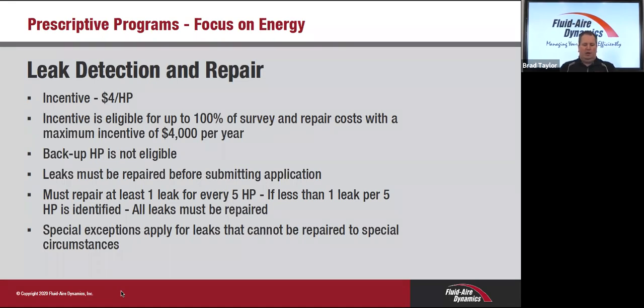So Focus on Energy has offered an incentive of $4 per running horsepower. This does not include backup compressors in that number. The incentive is eligible for up to 100% of the survey and repair costs with a maximum incentive of $4,000 per year. Leaks must be repaired before submitting an application, and you must repair at least one leak for every 5 horsepower. Otherwise, they will restrict how much they pay out. And some exceptions may apply for leaks that cannot be repaired due to special circumstances, such as a large cylinder inside of a production machine that can't be shut down, or maybe that cylinder cup seal is not available anymore. But I'd appreciate it if you could expand on this a bit more, Laura.